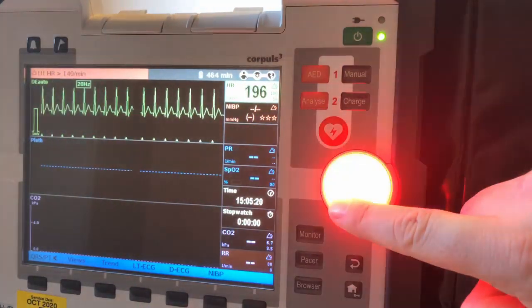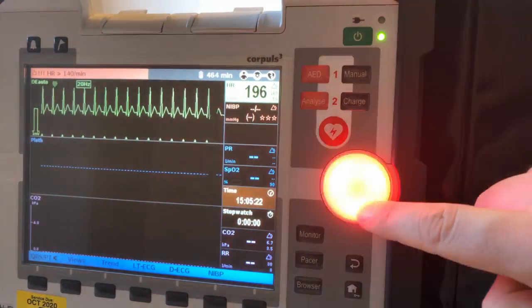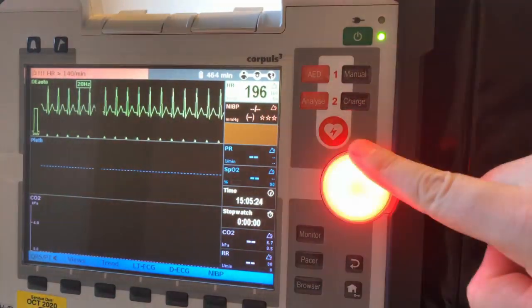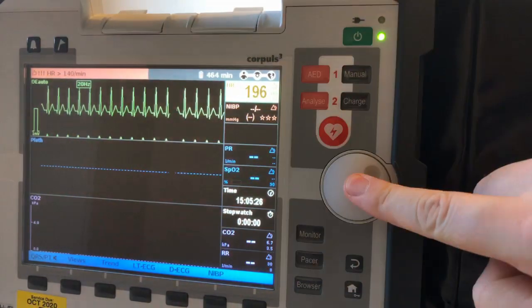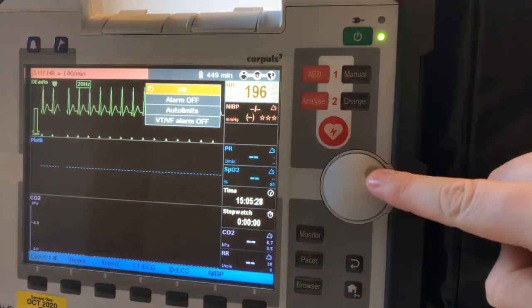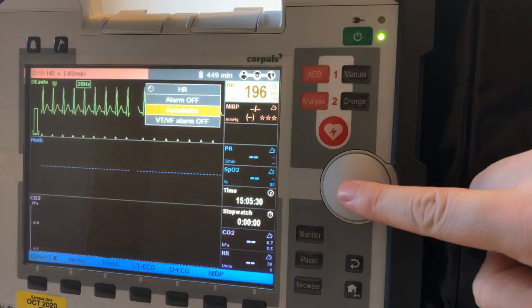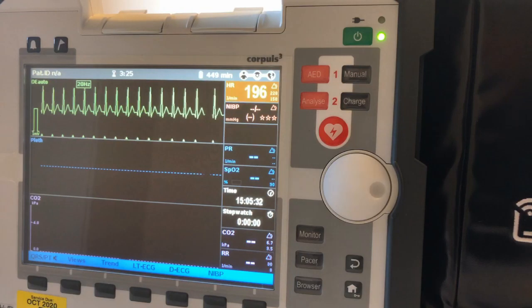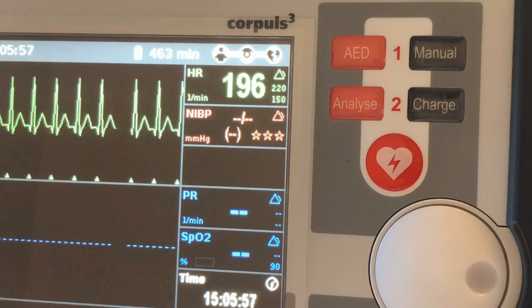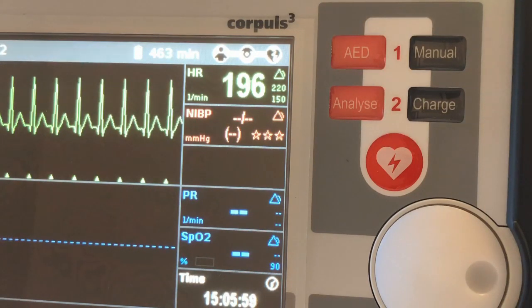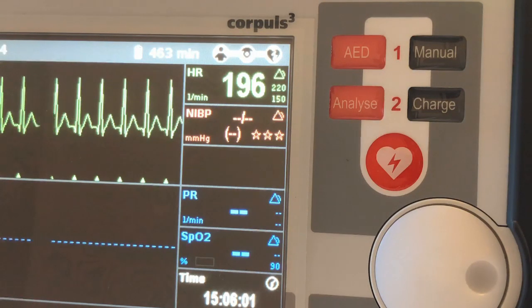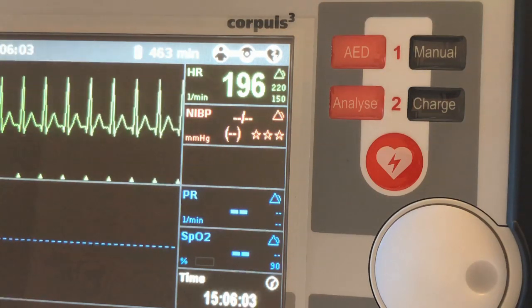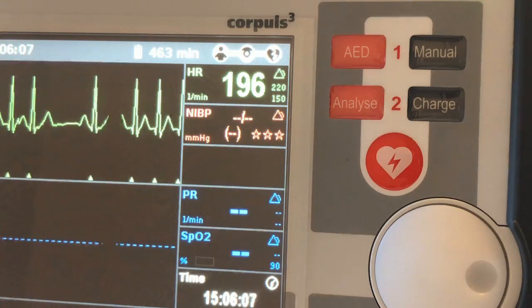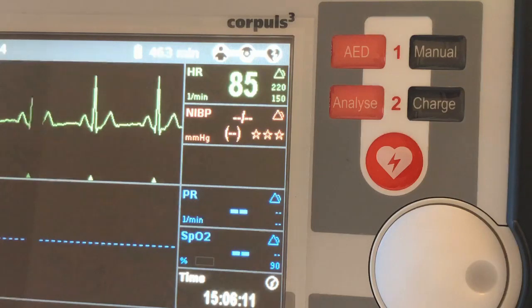If a patient has a high heart rate and you wish to amend the alarm limits to reflect this, you can do so by using the Auto Limits function. Use the jog wheel to scroll to the appropriate field on the screen and select the Auto Limits option from the submenu. This will reset the alarm limits based on the current value to 30% above and 30% below the number displayed. If the condition of the patient changes, you can repeat this process.